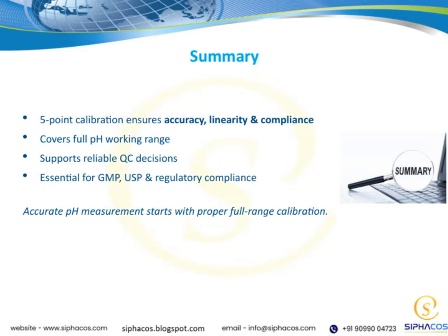First, a 5-point calibration is crucial because it ensures accuracy, linearity, and compliance in our pH measurements. This means our readings are precise across the entire pH range we work with. Speaking of which, it covers the full pH working range, so no matter what sample we're testing, we're confident in our results. This thorough calibration supports reliable quality control decisions, which are vital for maintaining product standards.